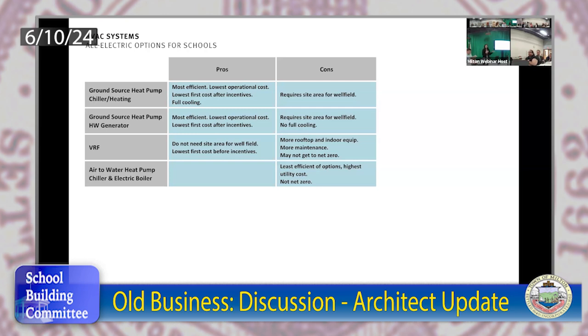The VRF, the pro would be that you don't need site for the well field, because you don't put any wells in, it's all contained in the building on the roof, and it is the lowest first cost before incentives, but not after. And so on the con side, typically with ground source, it's, do we have space? Can we put the well field in? We do have space on this particular site, so we can put a well field in. And then on the VRF, it's more rooftop equipment, it's also more indoor equipment, has more maintenance. If you imagine that diagram where it shows in every ceiling, you have all these equipment components that need filters and have motors, and there's a lot more equipment and maintenance. It may not get to net zero.